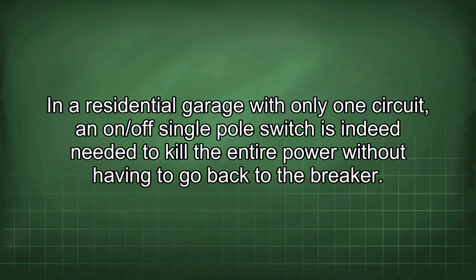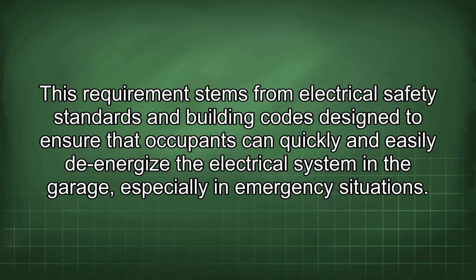In a residential garage with only one circuit, an on/off single-pole switch is indeed needed to kill the entire power without having to go back to the breaker. This requirement stems from electrical safety standards and building codes designed to ensure that occupants can quickly and easily de-energize the electrical system in the garage, especially in emergency situations.